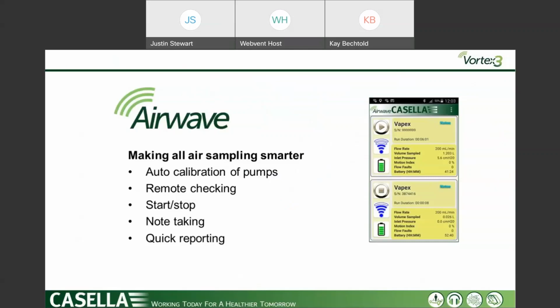One thing Airwave does as well is we'll work in conjunction with our Flow Detective. It allows you to do the calibrations of the pump. You can do remote checking, the starting and stopping. What you also can do with the calibration side is you can also use the Flow Detective and calibrate within less than 10 seconds. And it does a full loop calibration, which we'll talk about here in the upcoming slides.